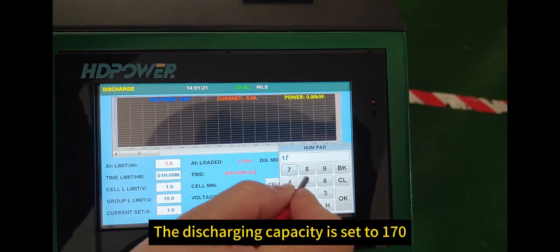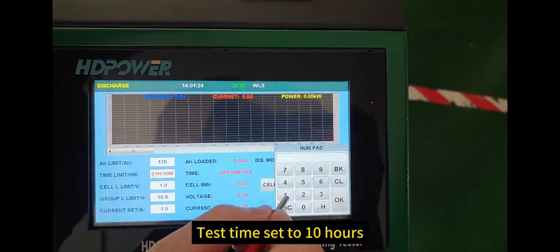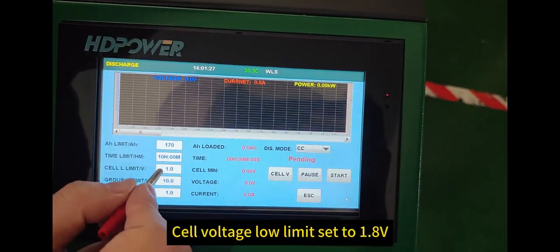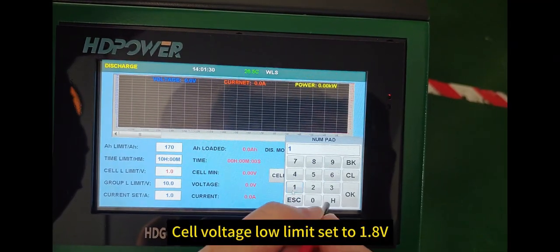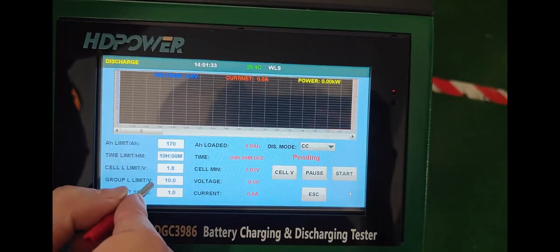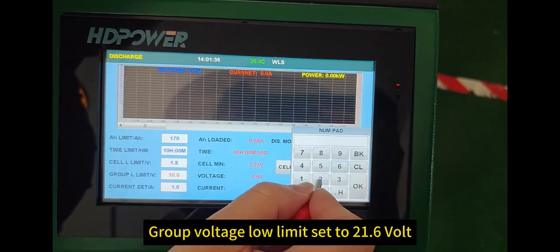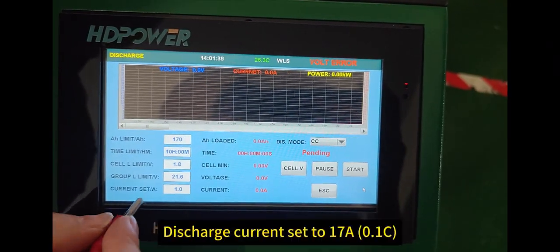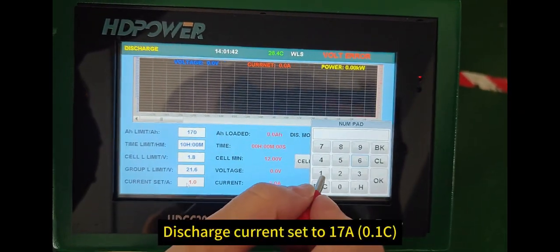The discharging capacity is set to 170. Test time set to 10 hours. Cell voltage low limit set to 1.8 V. Group voltage low limit set to 21.6 volt. Discharge current set to 17A (0.1C).